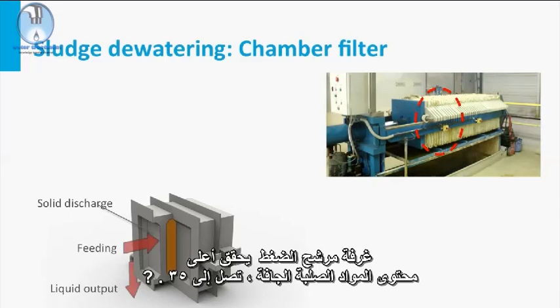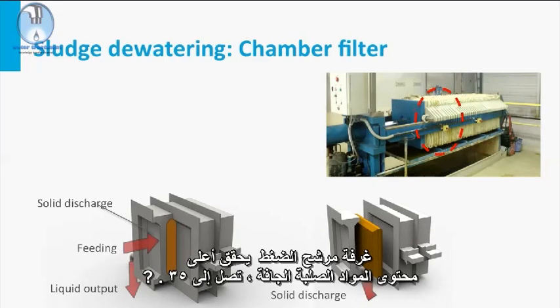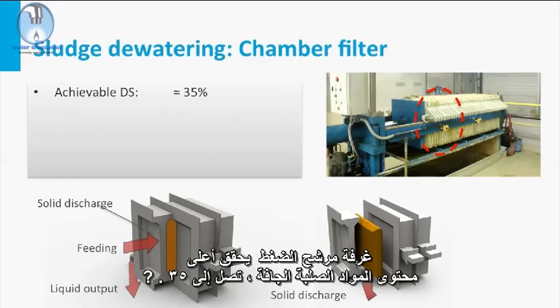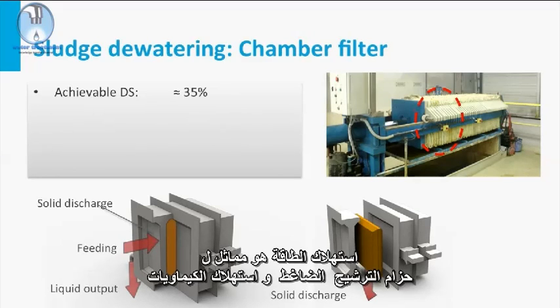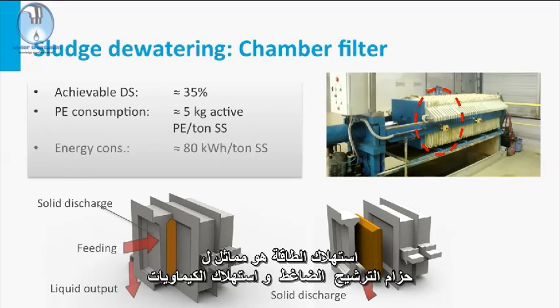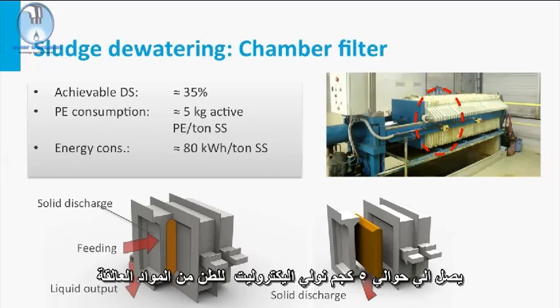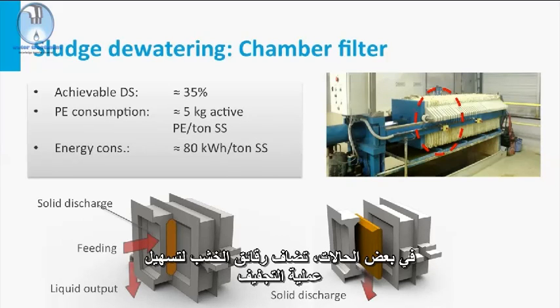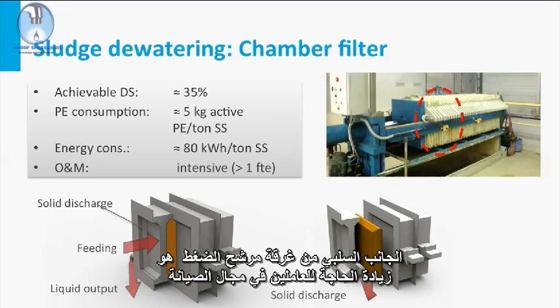The chamber filter press achieves the highest dry solids content, reaching up to 35%. The energy consumption is similar to the filter belt press, and the chemical consumption reaches about 5 kilograms PE per ton SS. In some cases, wood chips are added to facilitate the drying process. The downside of the chamber filter press is the high demand for maintenance personnel.